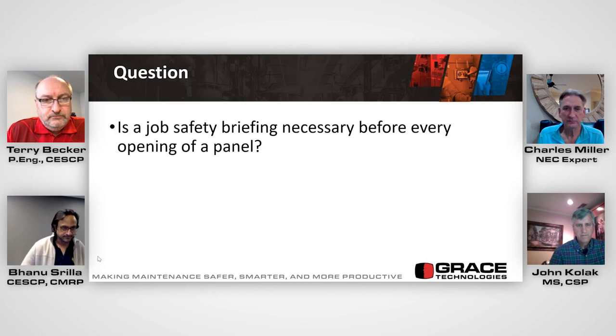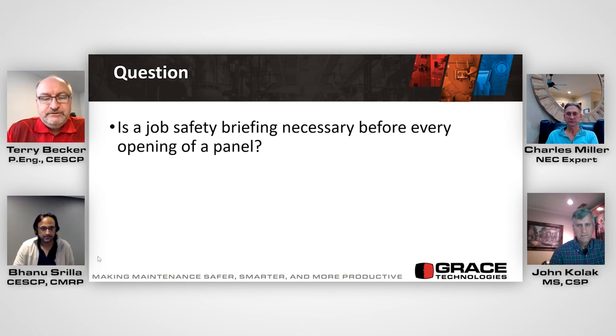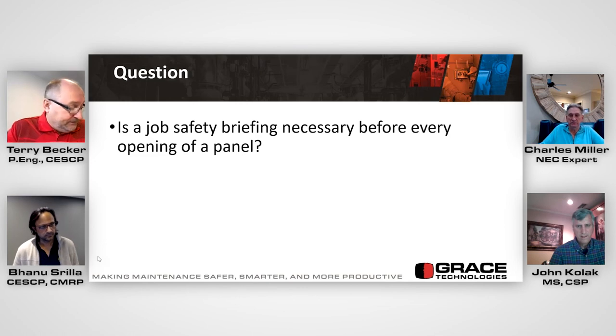John and Terry: it's needed every time you're exposed to arc flash and shock hazards. It's independent of what you do next. You need to define the work task, and then 70E and Z462 - well, before they even said it, this should have been the case, right? Some sort of job safety plan, writing some information down. So, but explicitly in Article 110.5(I), you have to document your job safety plan before you're exposed to arc flash and shock hazards.